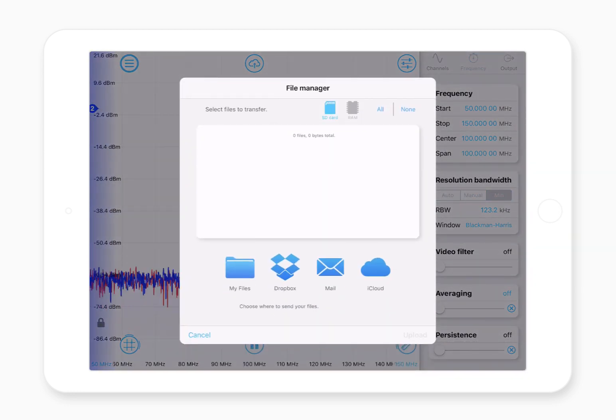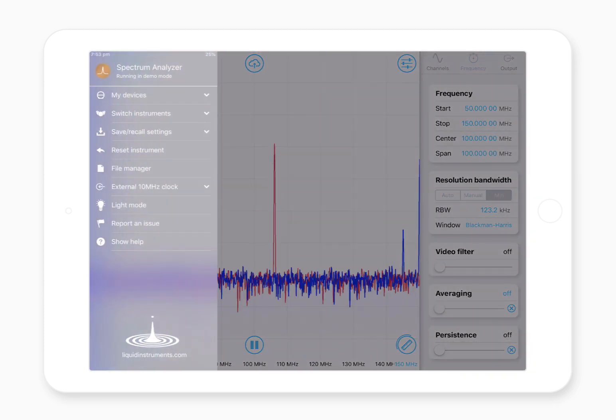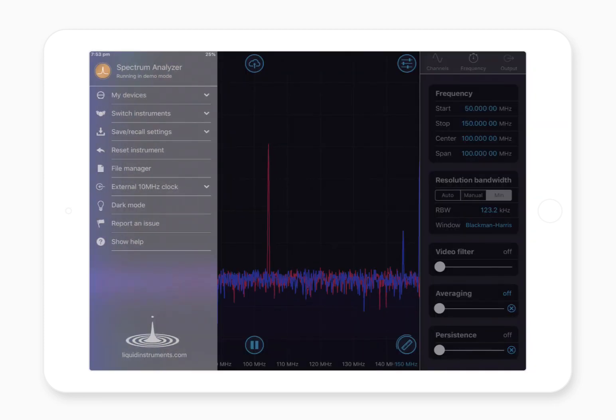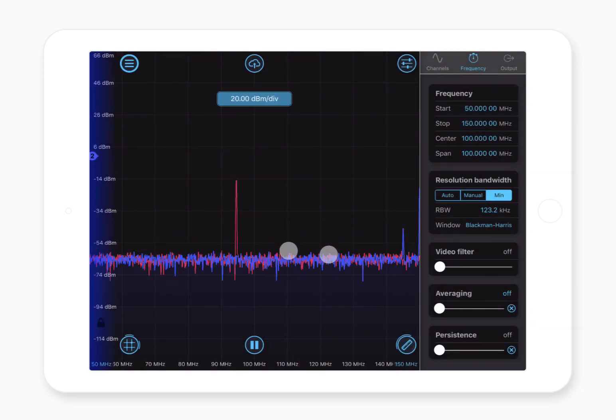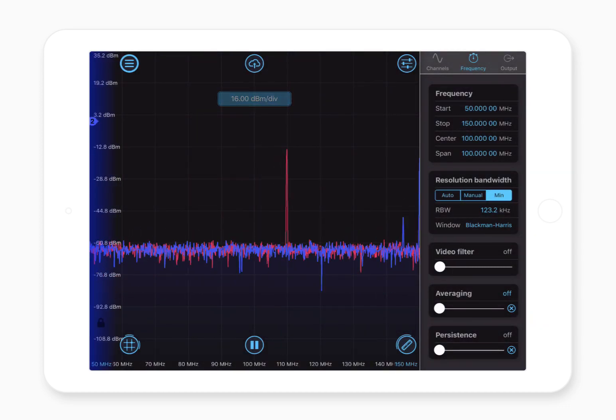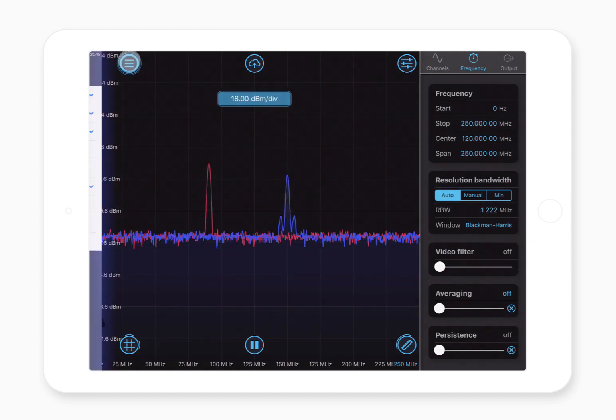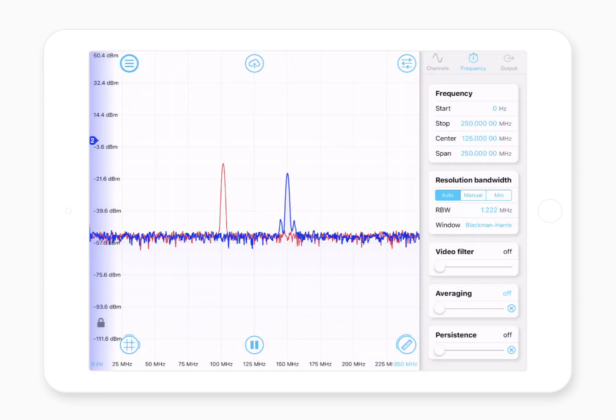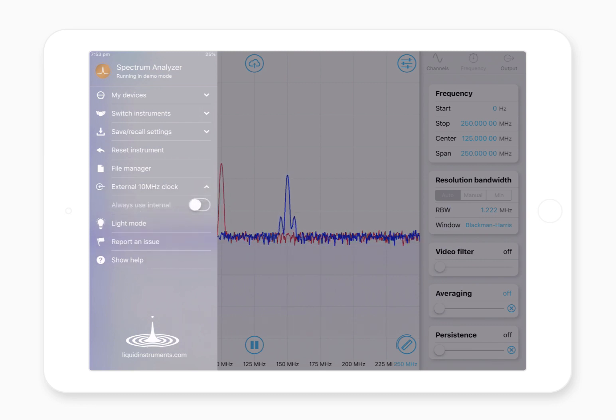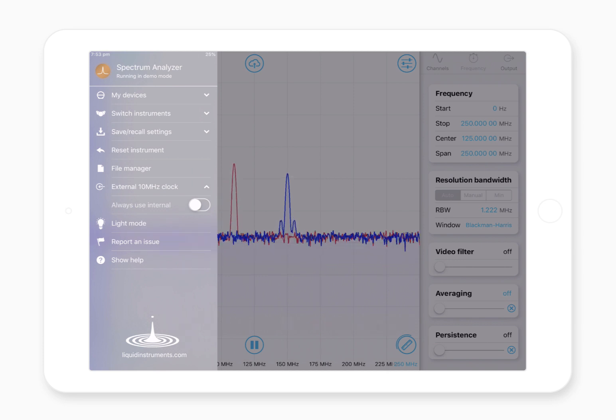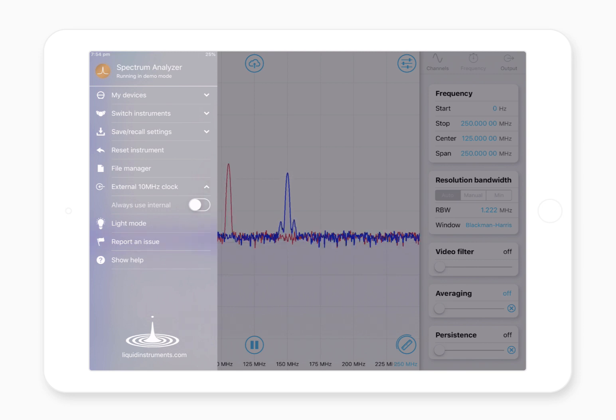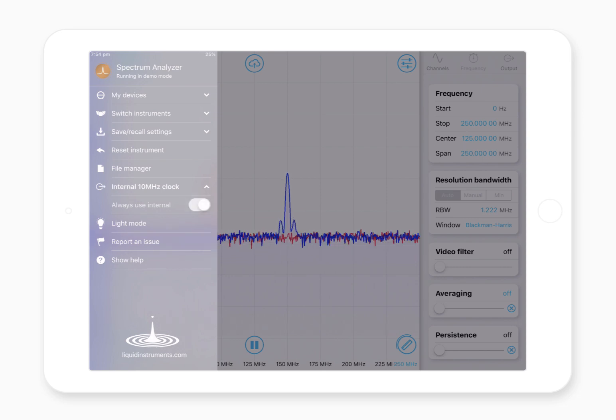You can also access files, which is useful if you've saved a bunch of data and want to manage it all. There are also options like changing to dark mode — if you work in a dark lab, this is a lifesaver. And you've also got the external 10 MHz reference clock option. When you connect an external 10 MHz reference to Moku Lab, it'll automatically detect and phase-lock to that reference, but if you didn't want it to do that for any reason you can force it to use the internal clock.